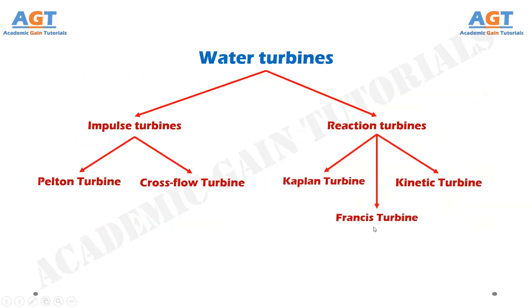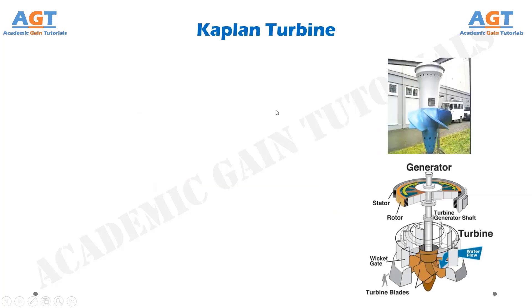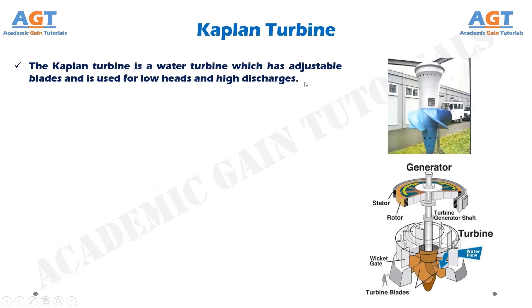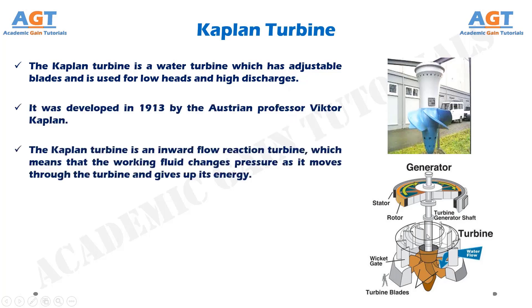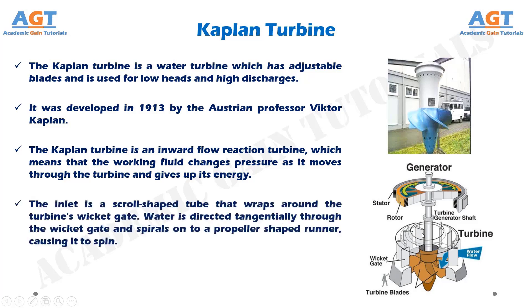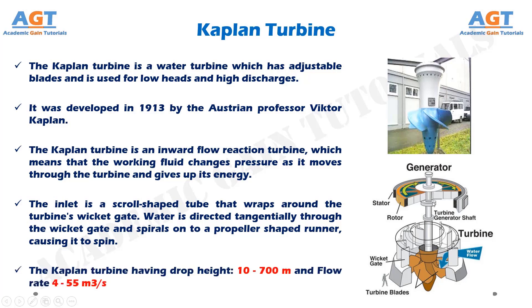The three types are: Kaplan turbine, Francis turbine, and kinetic turbine. The Kaplan turbine is a water turbine which has adjustable blades and is used for low heads and high discharges. It was developed in 1913 by the Austrian professor Viktor Kaplan. The Kaplan turbine is an inward flow reaction turbine, which means the working fluid changes pressure as it moves through the turbine and gives up its energy. The inlet is a scroll-shaped tube that wraps around the turbine's wicket gate. Water is directed tangentially through the wicket gate and spirals onto a propeller-shaped runner, causing it to spin. The Kaplan turbine has a flow rate of 4 to 55 cubic meters per second.